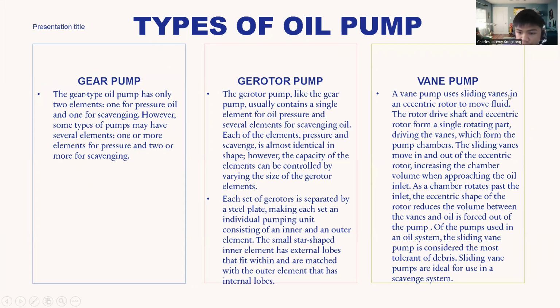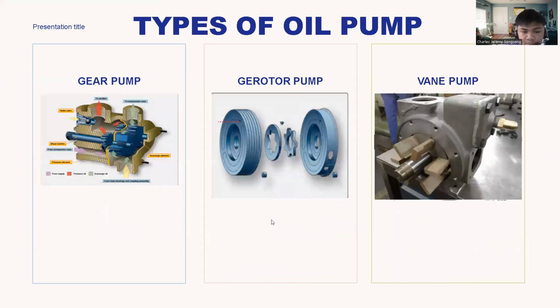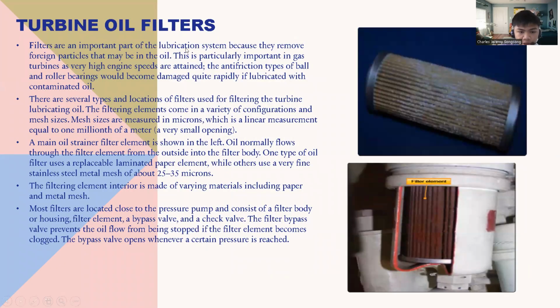A vane pump uses sliding vanes in an eccentric rotor to move the oil. The rotor drive shaft and eccentric rotor are made from a single rotating part. This is what they look like. Next is turbine oil filters. Filters are an important part of the lubrication system because they remove foreign particles that may be in the oil. This is particularly important in gas turbines, as we need a high engine speed, so the anti-friction types of ball and roller bearings would become damaged quite rapidly if we did not filter the contaminated oil.